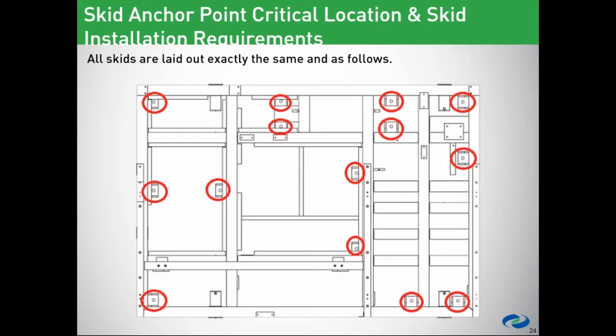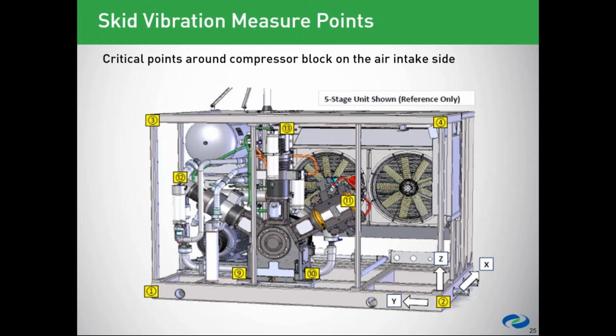Move along. So, skid vibration measuring points. The compressor block was the key point that was measured in the past for commissionings, and now we're going to use all of these yellow connections on the X, Y, Z axes, and we're going to measure the skid. This is going to be the basis for health monitoring of the system, and this is the intake side of the compressor skid being shown. This is the discharge view, and we have 4 corner points to measure here.